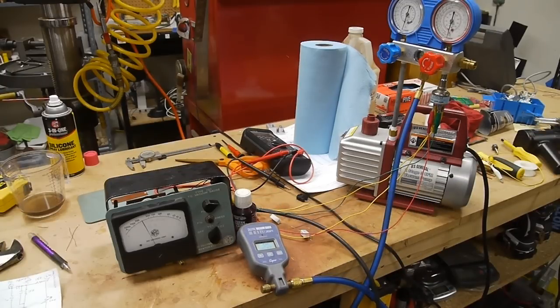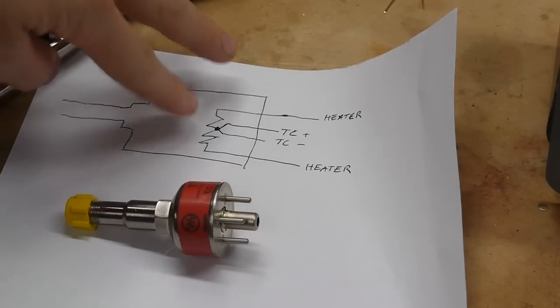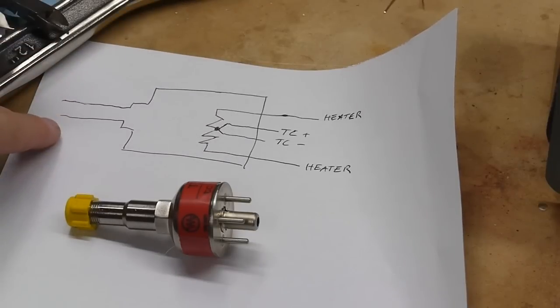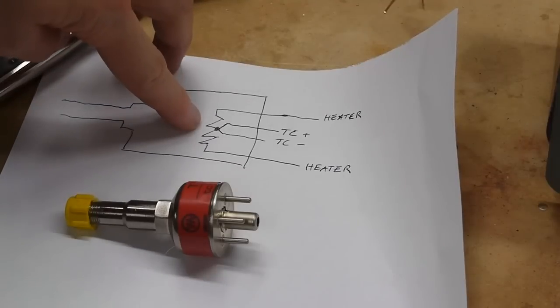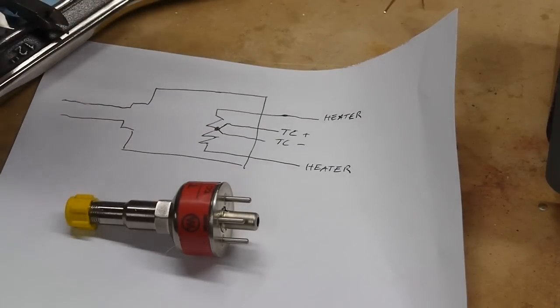Let me show you how this thing works. The vacuum sensor itself is a four wire device. Two wires are connected to a heater inside this envelope, which connects to your vacuum system. On the heater there's a thermocouple, so there's four total. The idea is that you run a specified current through the heater circuit, in this case something like 165 milliamps, and the resistance of the heater is about an ohm and a half. If the vessel here is full of air, the heater will be cooled down by all of the conduction mostly in the air.